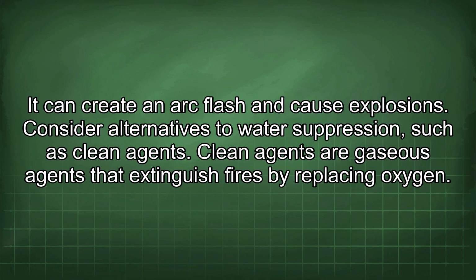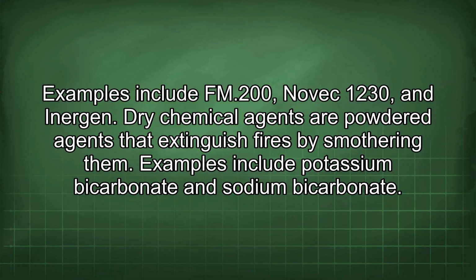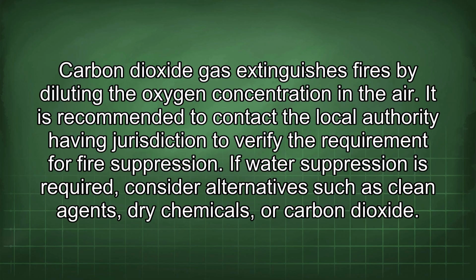Consider alternatives to water suppression, such as clean agents. Clean agents are gaseous agents that extinguish fires by replacing oxygen. Examples include FM200, Novec 1230, and Inergen. Dry chemical agents are powdered agents that extinguish fires by smothering them. Examples include potassium bicarbonate and sodium bicarbonate. Carbon dioxide gas extinguishes fires by diluting the oxygen concentration in the air.